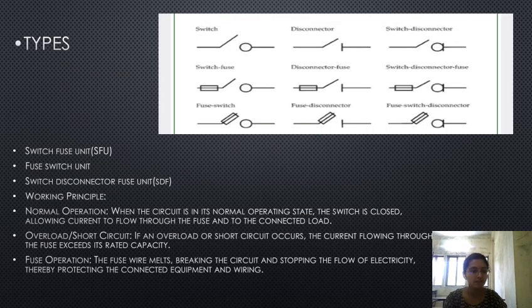Types of SFU. First one, switch fuse unit. Second one, fuse switch unit. Third one, switch disconnector fuse unit. And the working principle of SFU is: in normal operation, when the circuit is in its normal operating state, the switch is closed, allowing current to flow through the fuse and to connected load. Overload or short circuit. If an overload or short circuit occurs, the current flowing through the fuse exceeds its rated capacity. Fuse operation. The fuse wire melts, breaking the circuit and stopping the flow of electricity, thereby protecting connected equipment and wiring.